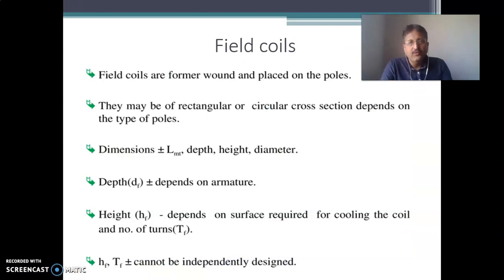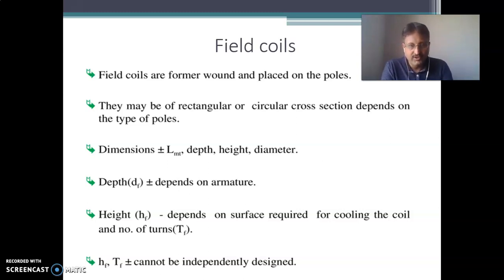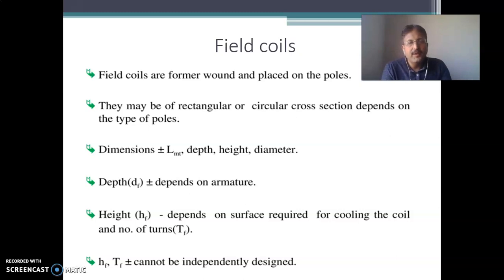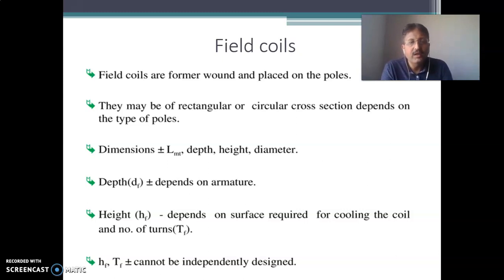The field coils are former wound and they are placed over the poles. The field coils may be of rectangular shape or a circular cross section area depending upon the type of the pole. The main dimensions of the field coil are: LMT — length of mean turn of the field winding — depth of the field winding, and height of the field winding which depends upon the surface required for cooling of the coil and the number of turns.